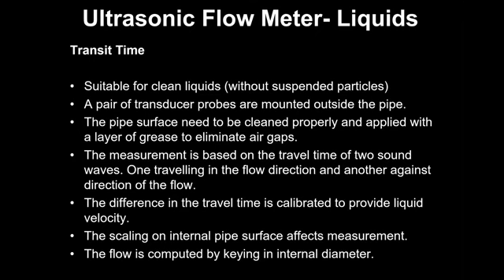If there is scaling on the pipe, either internally or externally, it is going to affect the measurement because the signal gets bounced. And you all know that if the surface is rough, it is going to bounce, like that's how the spin ball works. If it's a rough surface, it is going to have an unpredictable return path. So that is where the problem can be.